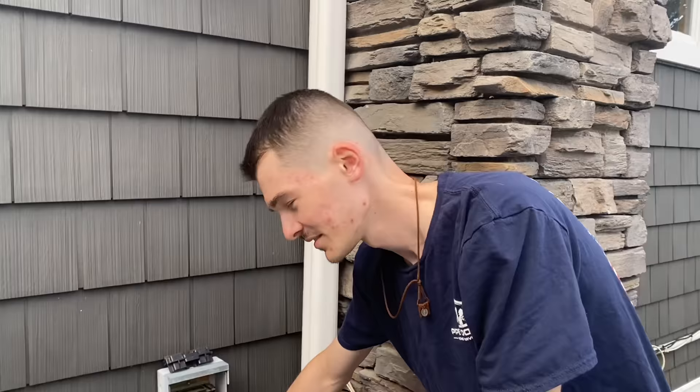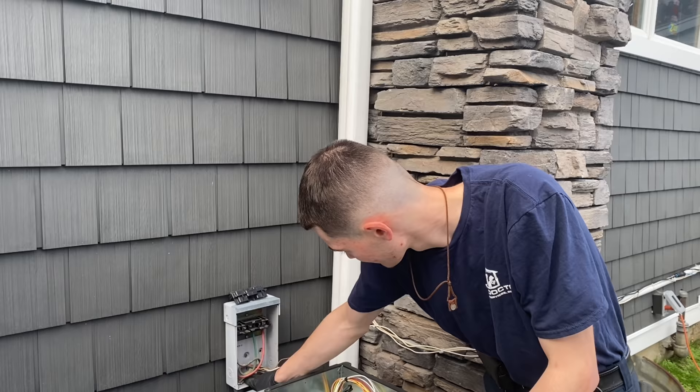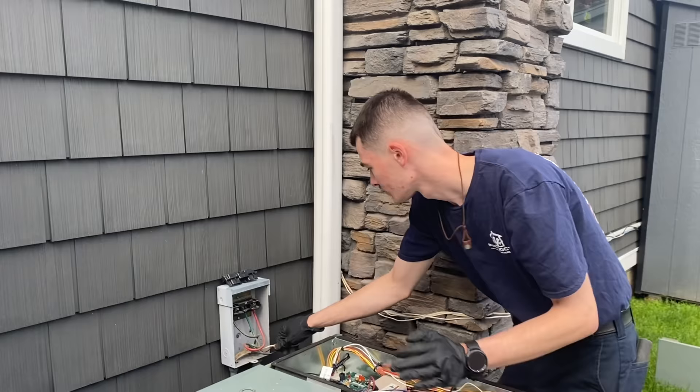We're doing a complementary visual integrity safety check on over 130 Navien units in the same building, and the first five we saw unfortunately all had the same symptom - a hole in the heat exchanger causing water to leak out. Not good.